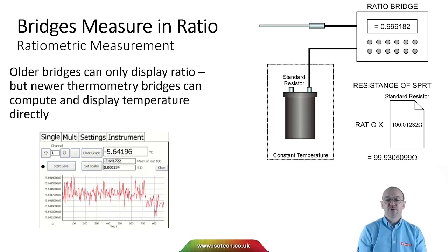The older bridges could only display ratio. You'd often see those in the laboratory with a number shown. But newer thermometry bridges can compute and display temperature directly. So inside the bridge there's a database containing the value of the standard resistors, probe coefficients, and a modern bridge can display temperature as well as ratio.